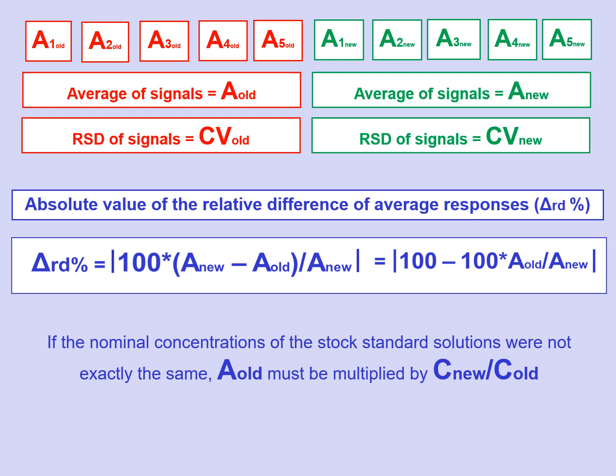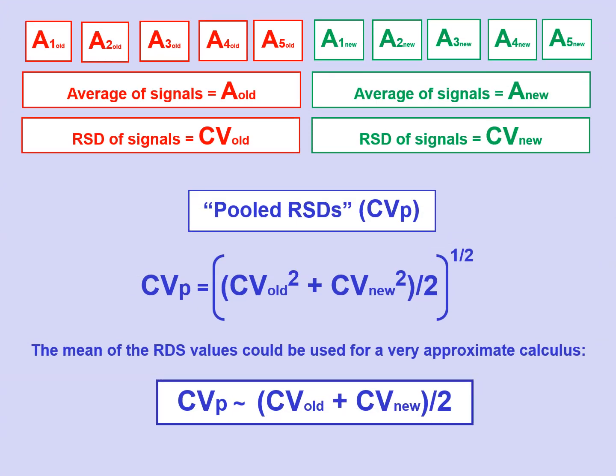In case the nominal concentration of the old standard C-old is not exactly equal to that of the new standard C-new, the mean response of the old standard A-old has to be multiplied by the quotient of the nominal concentrations of the new and the old standard, since it is the new standard that is taken as the reference. In addition, we have to calculate the weighted coefficient of variation CVp by taking the square root of the mean of the squares of the two coefficients of variation CV-old and CV-new. A very approximate value of CVp, valid for the intended purpose, can also be obtained simply as the arithmetic mean of both coefficients of variation: CV-old plus CV-new divided by two.